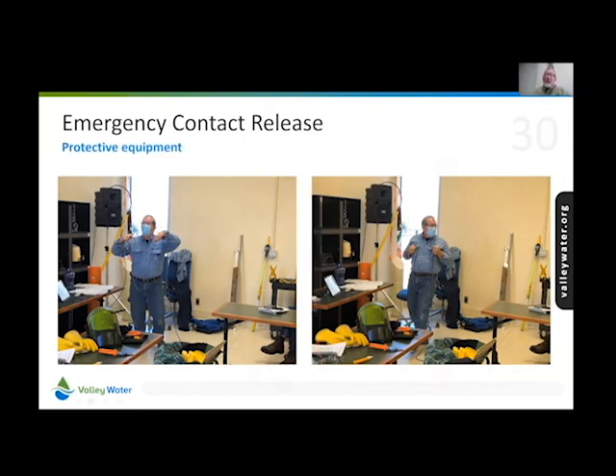Look in the background on this picture. This is a non-contact tester that we can use up to 132,000 volts. It'll also measure as low as 50 volts. That's one of the best units, and this one I send out yearly for calibration. Does that answer the question? Yeah, and this is tied to a fiberglass pole that's extendable, which is great to have. You can stand far away from the highest voltages I deal with at the water district, which is 21,000. It's nice to stand way back from that stuff and check to see if it's dead. This also has a self-test feature so you don't have to find a known source. That's really nice to have.